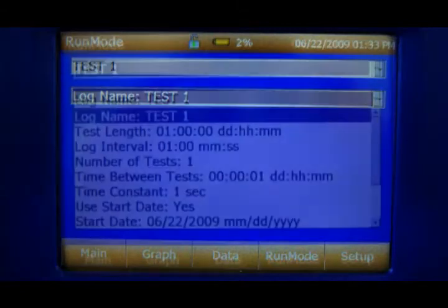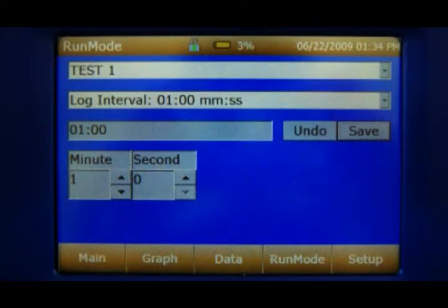From the second menu, now select Log Interval. The log interval is an averaging period for the DustTrack. What this means is that if the log interval is 1 minute, the instrument will log a sample every 1 minute, which is an average over that time. The log interval can be set to something smaller, like 1 second, which produces a lot of data, or something bigger, like 30 minutes, which is useful for very long sample periods. Most generally, the 1 minute interval is used. This works well for 24 or 48-hour sampling events.